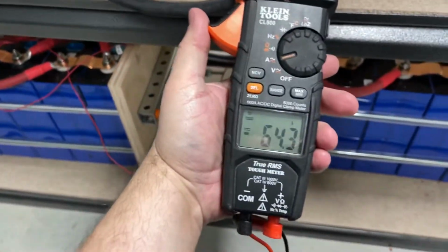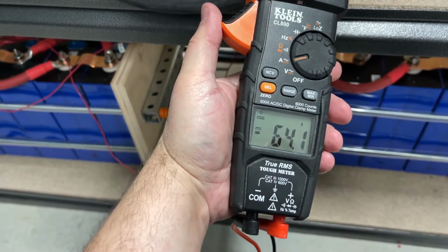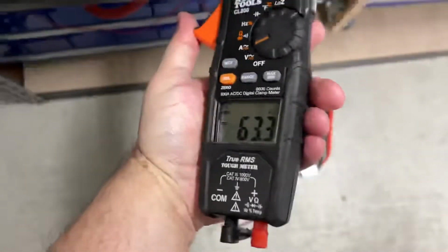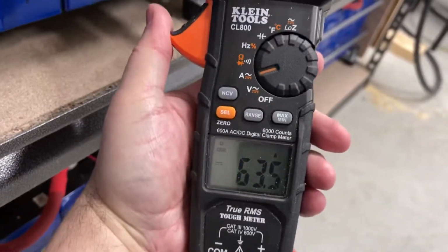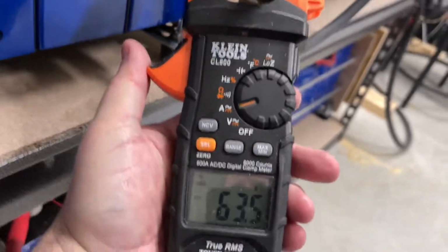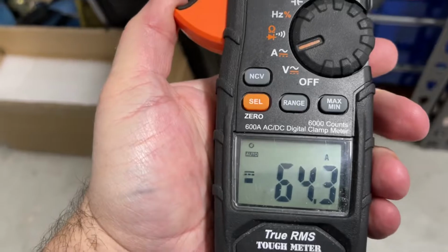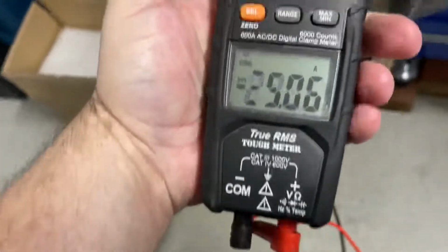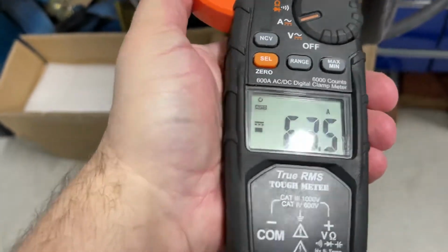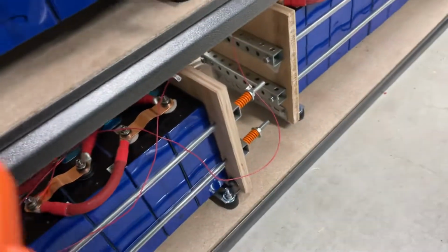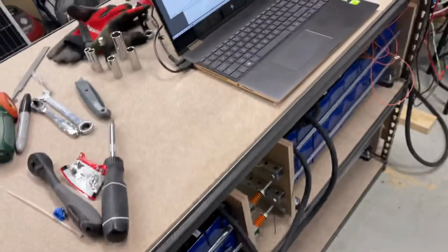So if I do this, I should observe half. I've got 64.1 amps here, let's see if I can get a better view of this, 63.5 amps here, so that's not bad, off by less than an amp. So if I do the same thing, 64.3, 63.5, and I've got another set of wires back there joining these two, and it's the same thing. So the amperage is being divided nicely.